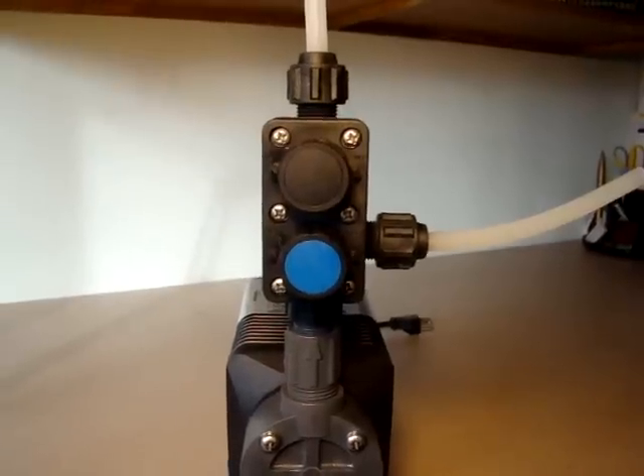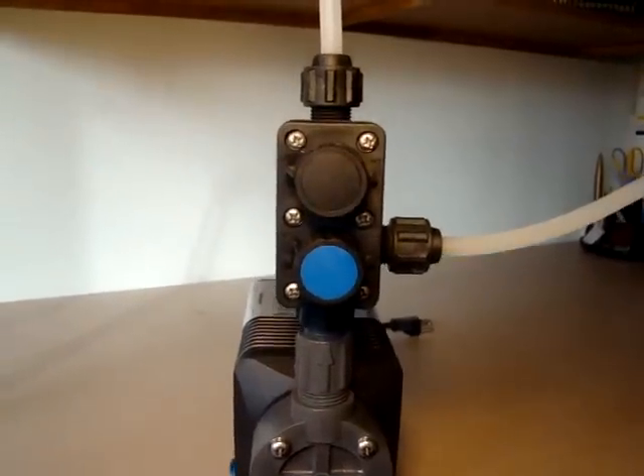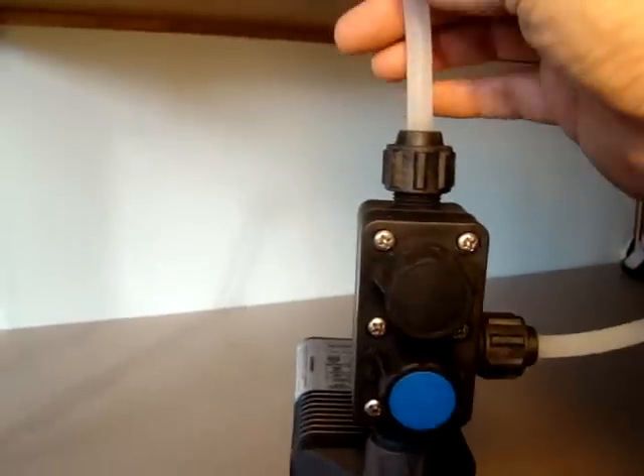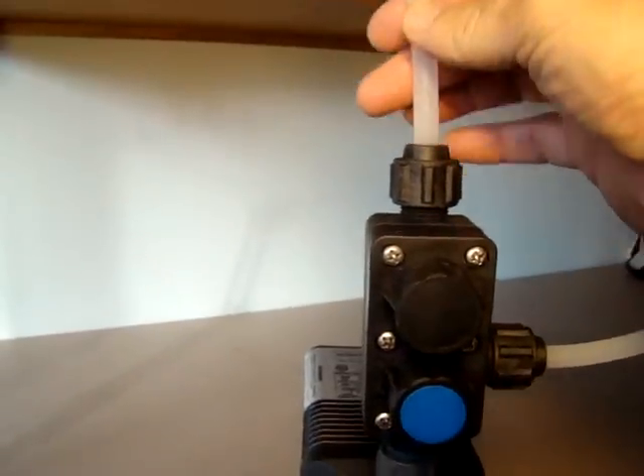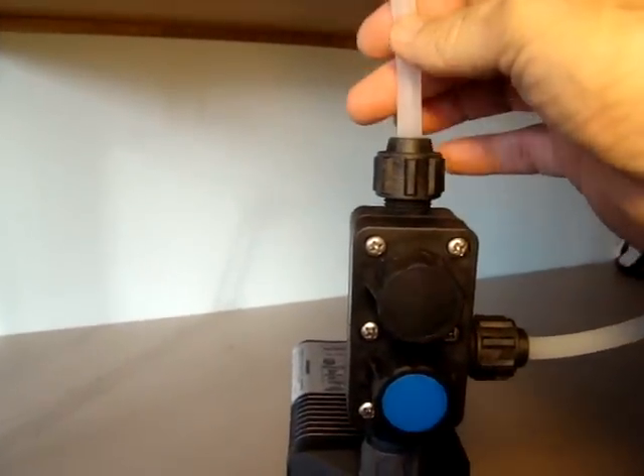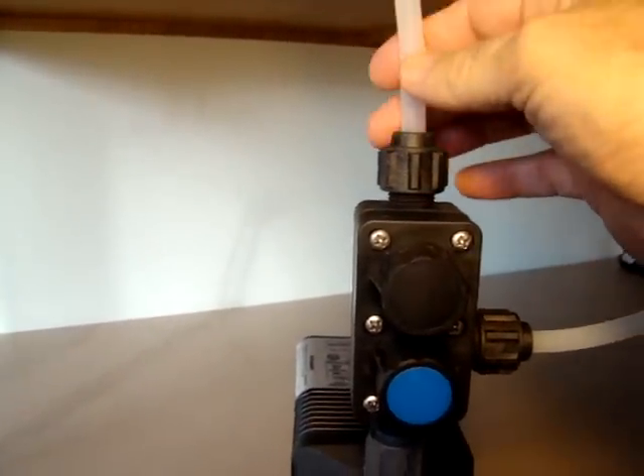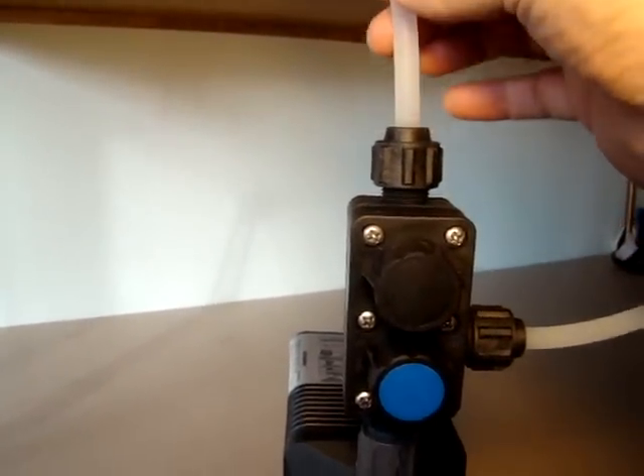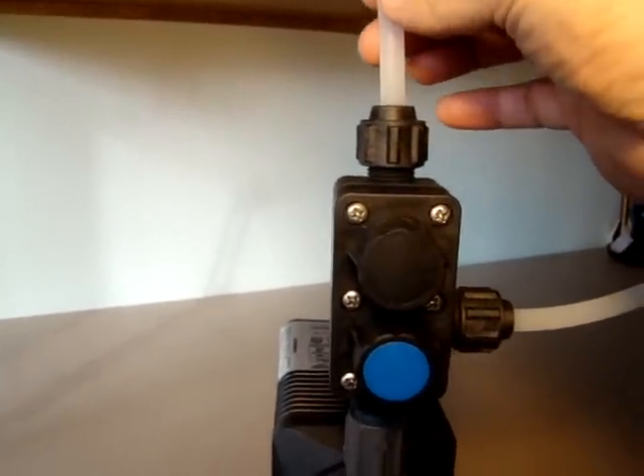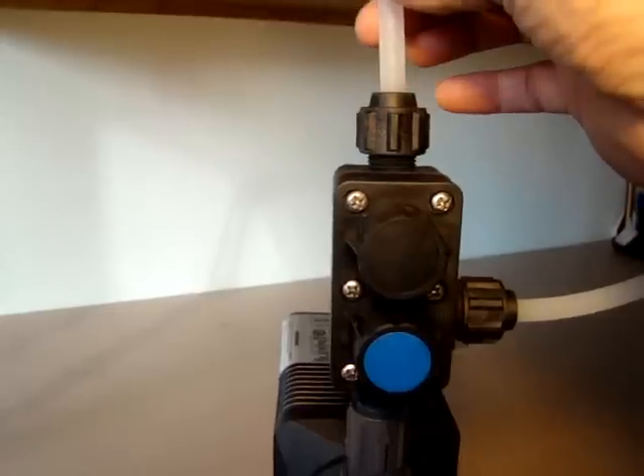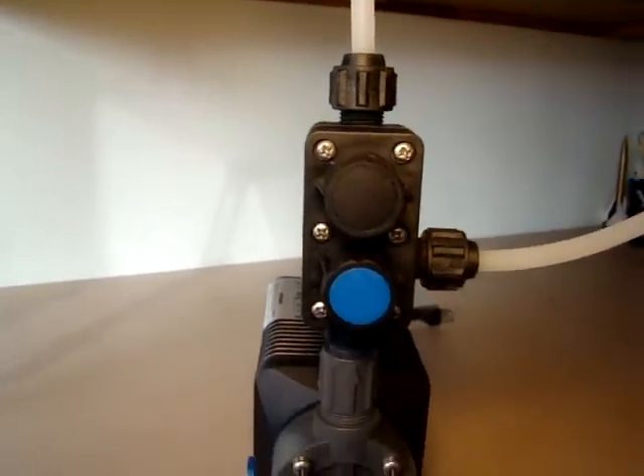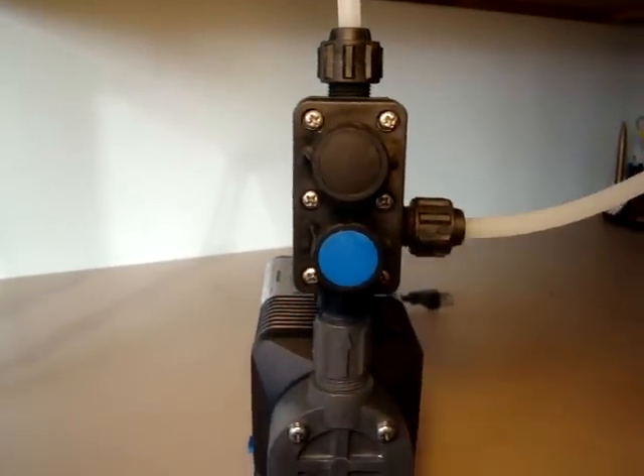So with the pump pulsing, the first thing you are going to do is you are going to feel this upper line to see if you can feel any pulsing in that line, which you should feel if it is in fact injecting liquid. If you don't feel any pulse, then you are going to proceed with the air bleed.